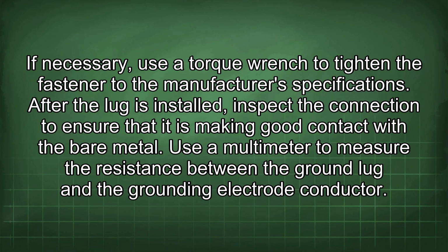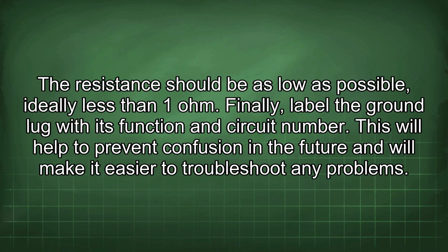Use a multimeter to measure the resistance between the ground lug and the grounding electrode conductor. The resistance should be as low as possible, ideally less than 1 ohm. Finally, label the ground lug with its function and circuit number. This will help to prevent confusion in the future and will make it easier to troubleshoot any problems.